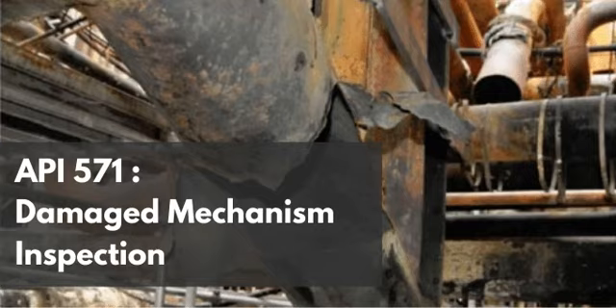What is that? The rolled area is the mechanical choke point of a heat exchanger. To understand the vulnerability, you really have to look at how a shell and tube heat exchanger is physically constructed. Okay, set the scene for us. You have a massive, thick, solid steel plate called a tube sheet. This plate has hundreds, sometimes thousands, of precision-drilled holes in it. You take your thin-walled copper alloy tube and you slide it into one of those holes.